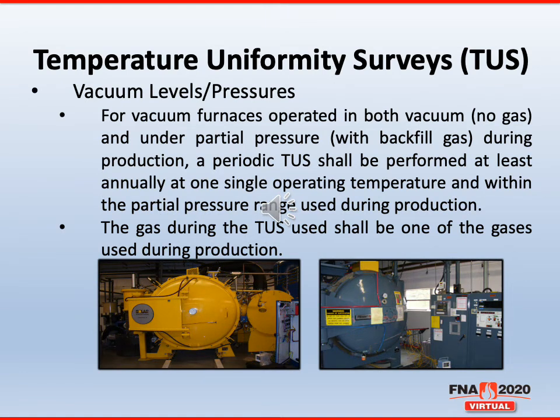So we addressed vacuum furnaces that are operated both in vacuum with no gas or under a partial pressure, with backfill gases such as argon, nitrogen, helium, during production. A periodic test shall be performed at least annually at one single operating temperature and within the partial pressure range during use for production. This is not an additional test. For instance, you have a vacuum furnace that needs 4 quarterly surveys during a year, and let's say you run a partial pressure of nitrogen anywhere between, let's say, 200 microns and 1,000 microns. All we're requiring is that you run one of those tests under a partial pressure in any part of the partial pressure range that is defined by the user. It's not a separate test, it's just a part of your quarterly testing process. We allow for any gas that may be used in production to be used for this partial pressure test.